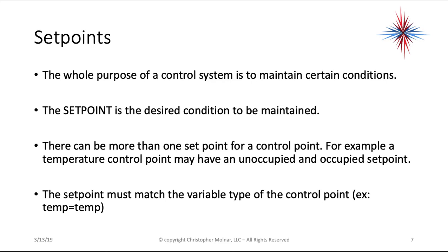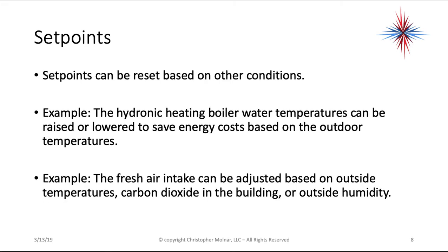Set points represent the desired condition to be maintained. The set point is the desired condition, and there can be more than one set point for a control point — for example, an unoccupied and an occupied set point. The set point must match the variable type of the control point. Set points can also be reset based on other conditions, such as hydronic heating boiler water temperatures raised or lowered based on outside temperature, or fresh air intake adjusted based on outdoor temperature, CO2, and humidity.